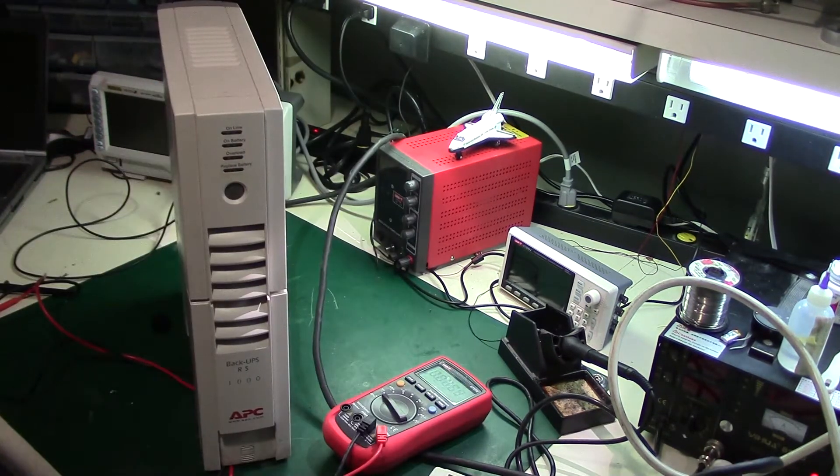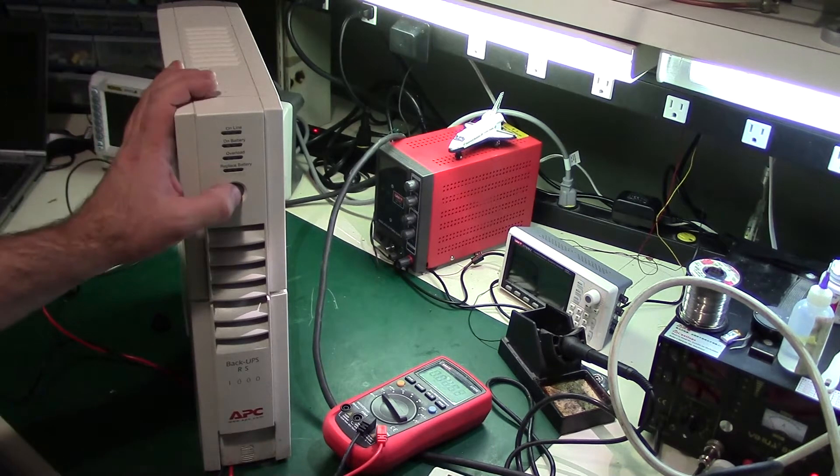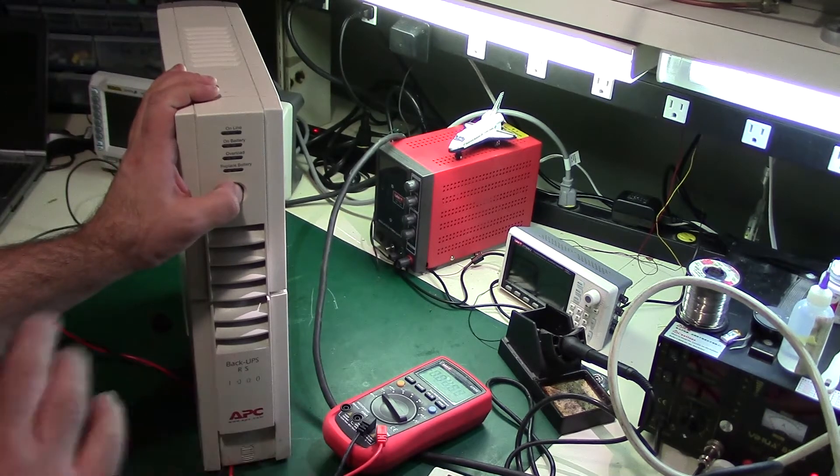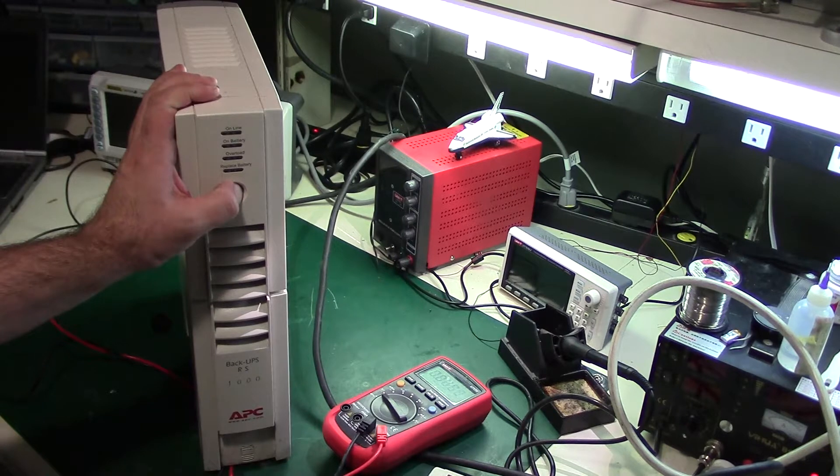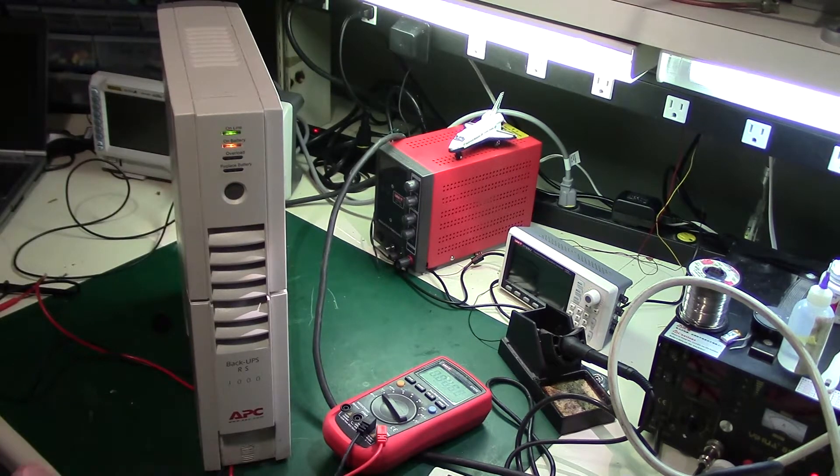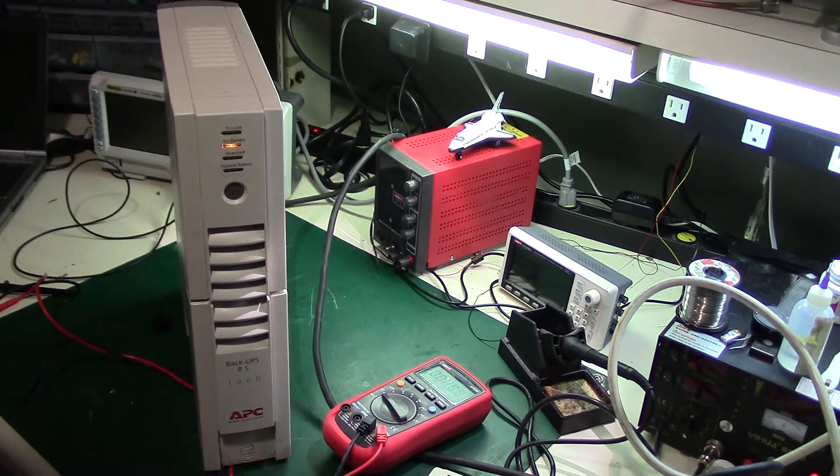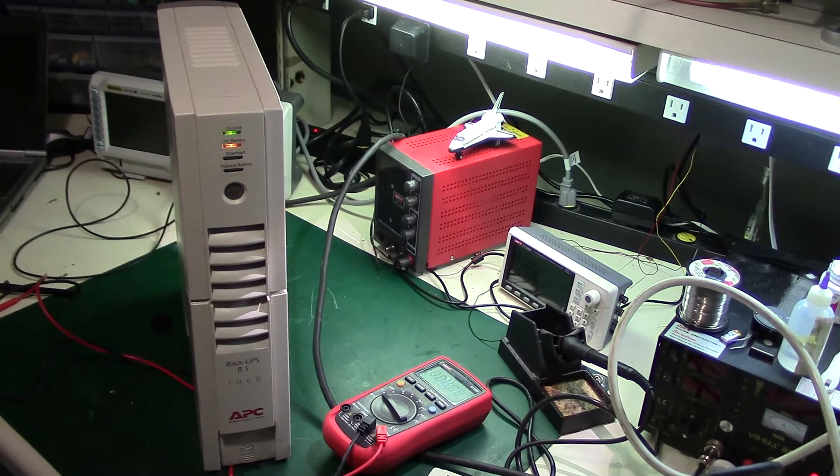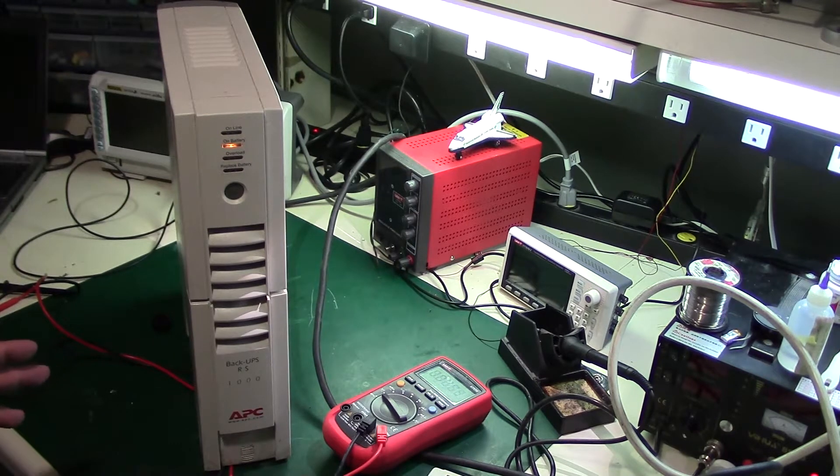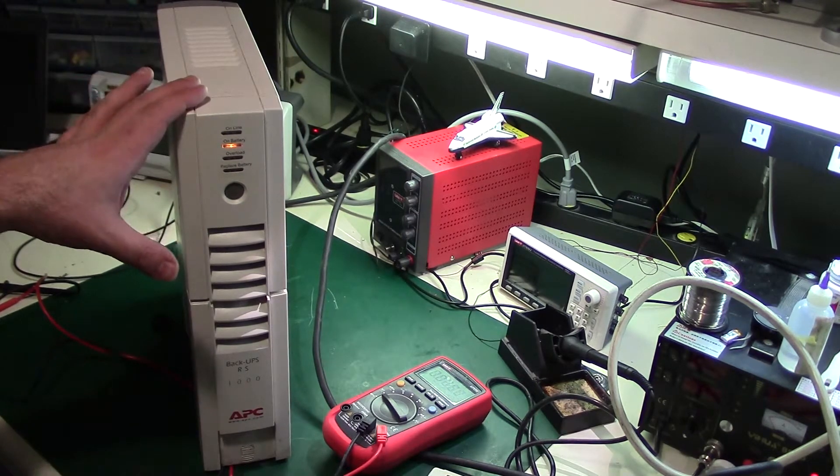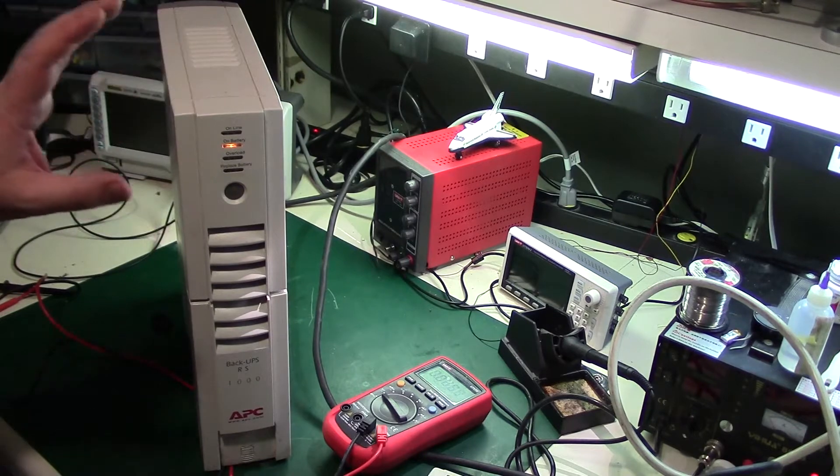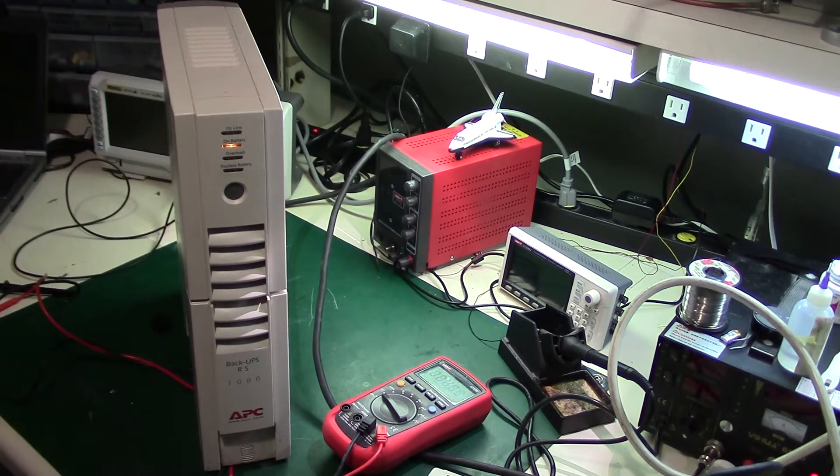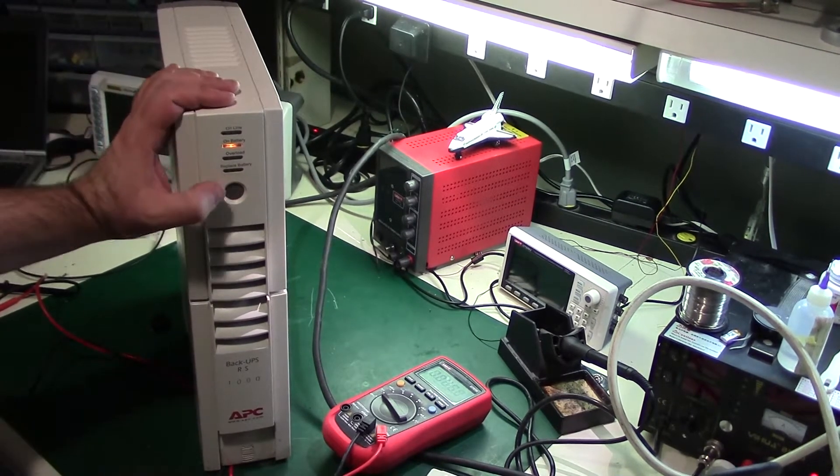You see, it does not come on with AC applied, but when I turn off AC, it will actually come on. And if I try to apply AC now, you'll see other than making some terrible noises, it just stays on battery. So this unit does not respond to AC power at all anymore.